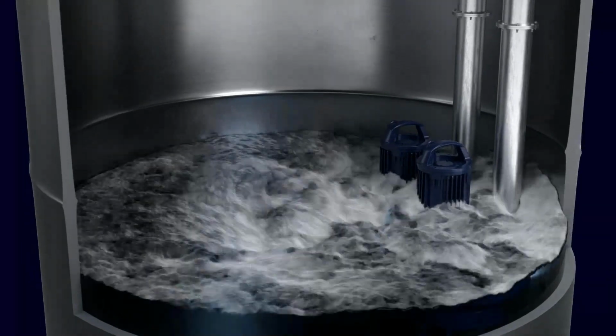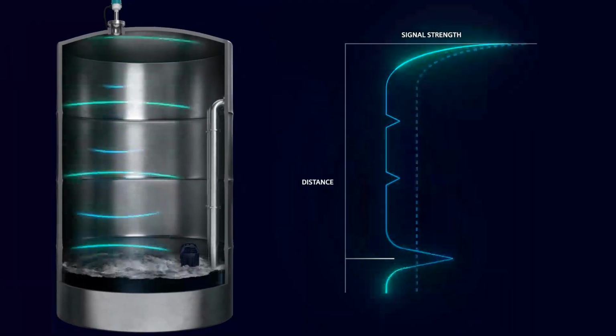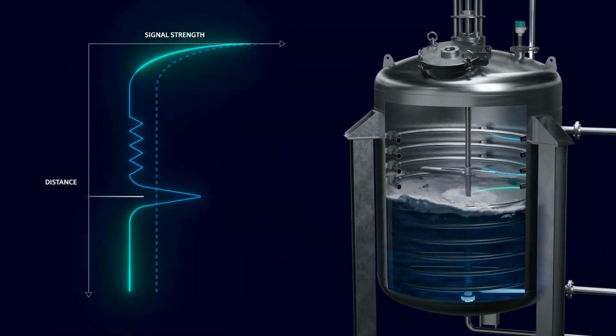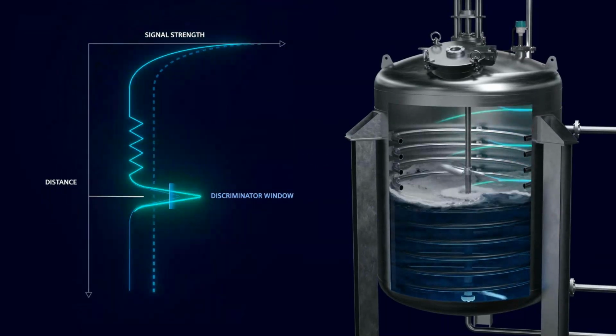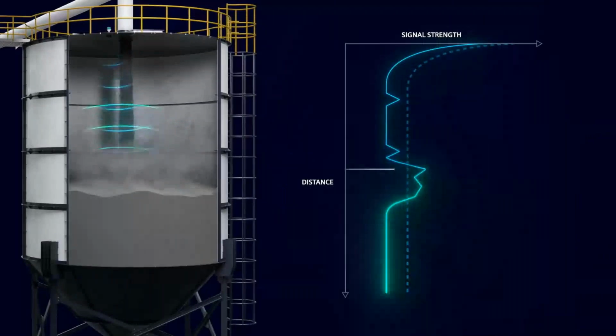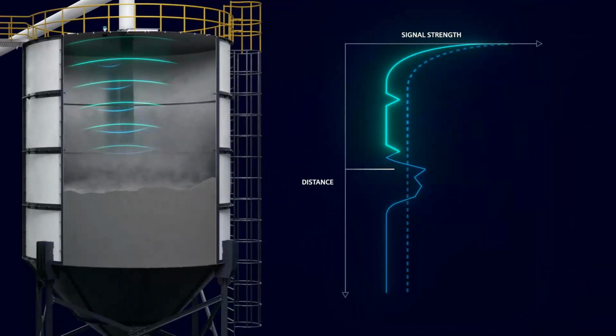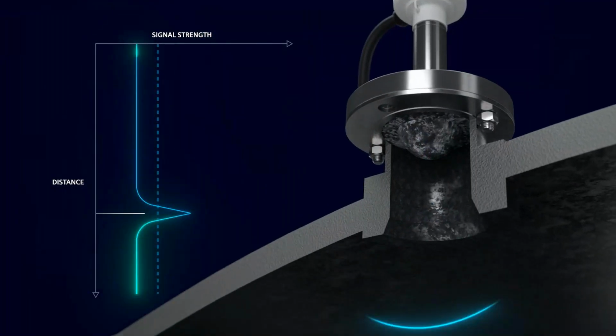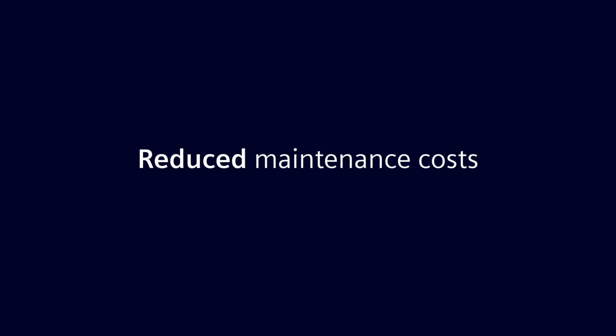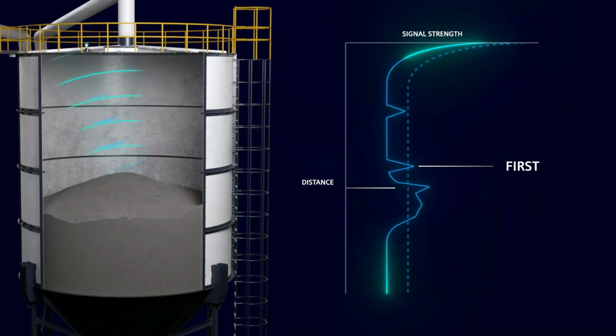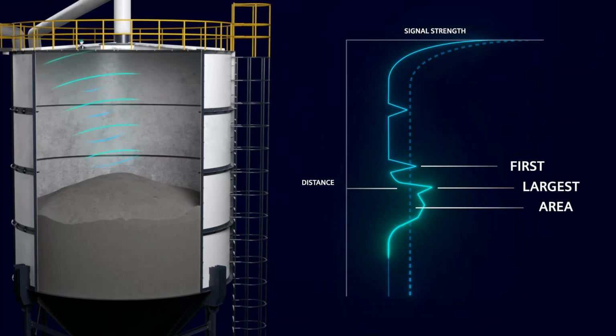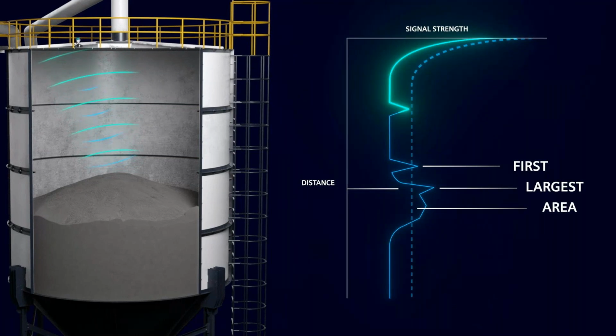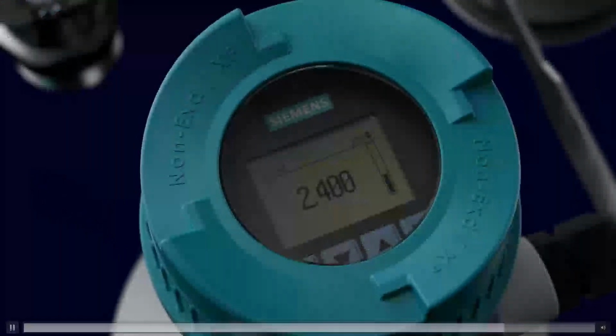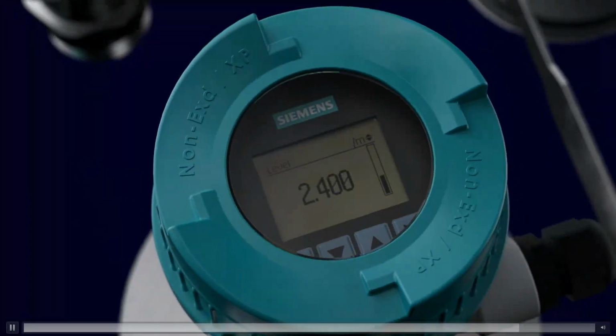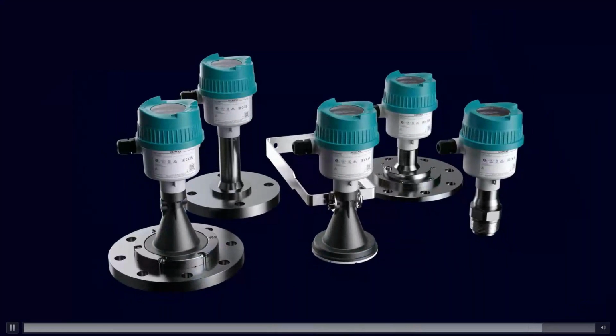Signal strength varies on dynamic surfaces, but even the weakest signal is strong enough for reliable measurements. The dynamic threshold curve reacts to the smallest changes when the signal is reduced, for example, in severe turbulence. Agitator blades are ignored by the discriminator window feature, as are echoes from silo seams. The new near-range suppression feature automatically suppresses signal buildup at the antenna over time, resulting in reduced maintenance costs. But sometimes it is not enough to just look at the first echo. Siemens uses first, largest, and area of the echo to determine the true level under challenging situations. Process intelligence enables reliable measurement in extremely demanding situations. This is why we build process intelligence into our devices, because it makes sense.